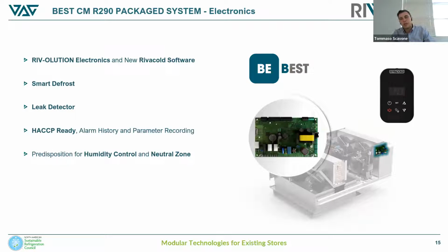Also, the new RIV-OLUTION electronics and the new software developed entirely by Rivacold guarantee efficiency, reliability and management flexibility. Again, ensuring perfect food preservation, easy control, and safety prevention. The smart defrost function has the ability to automatically manage the defrost cycles, timing, and duration, avoiding dangerous ice formation on the evaporator and thus guaranteeing optimal circuit operation. Practically, it works with an algorithm based on the information recorded by the temperature probes, pressure probes, and number of door openings. It adjusts automatically until it performs the perfect defrost cycle in terms of timing and duration according to that specific installation.